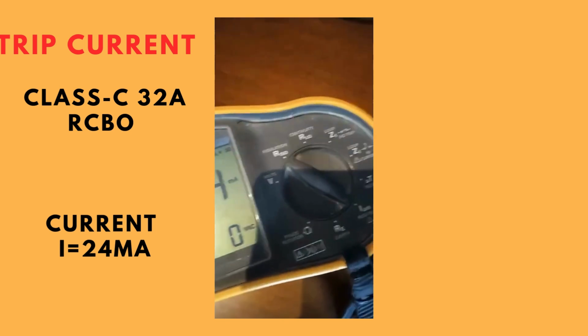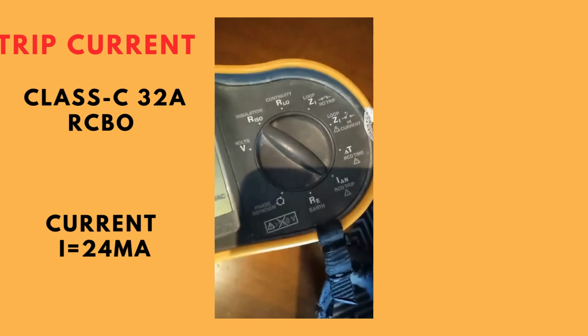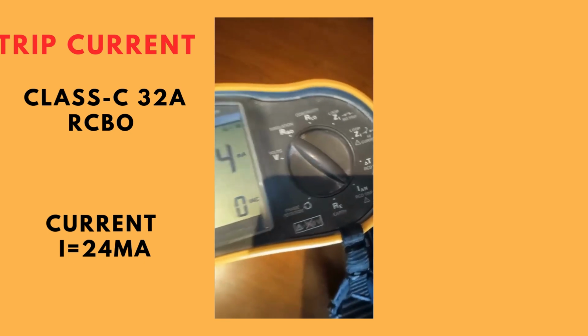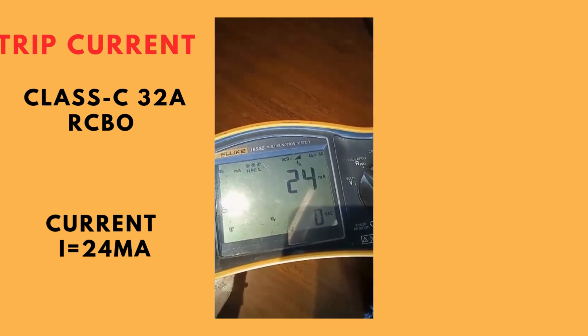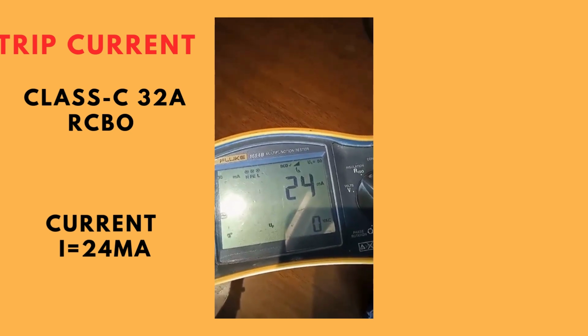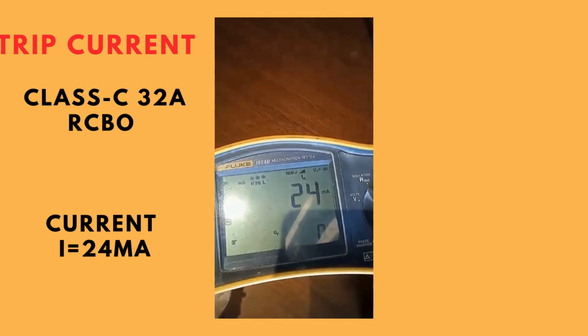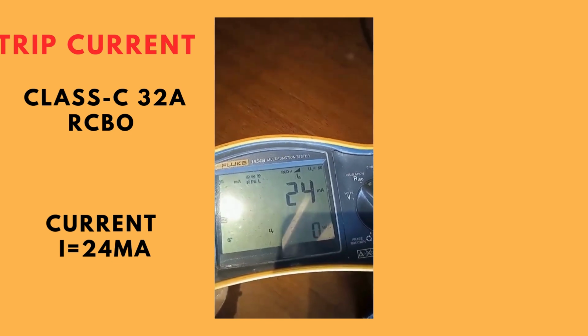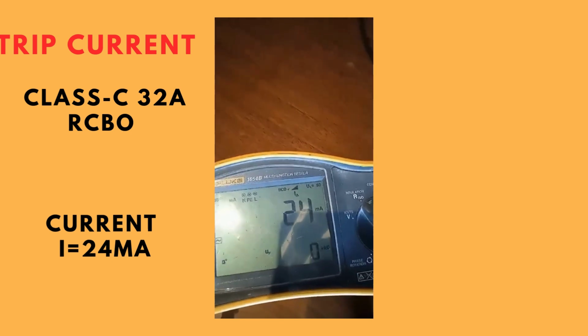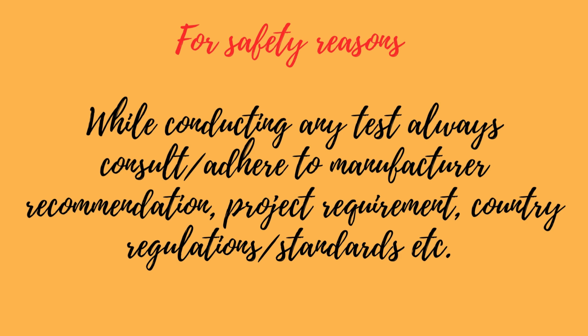Now the selector switch has been changed to trip current, as you can see. So we have a current of 24 milliamps after the circuit protective device has tripped, which is an RCBO 32 amps class C circuit breaker.